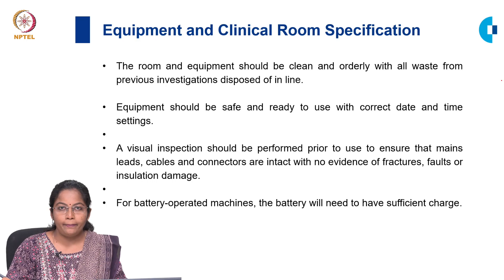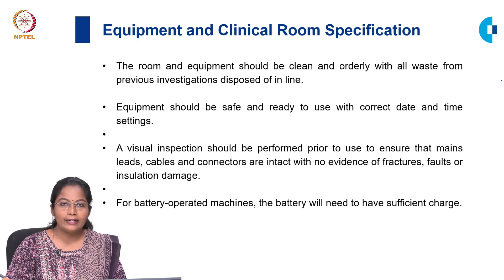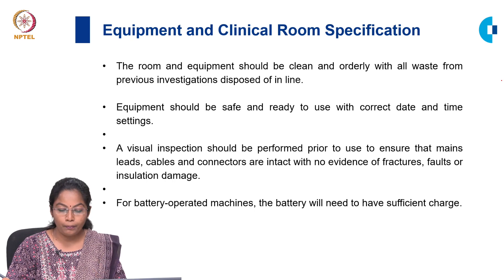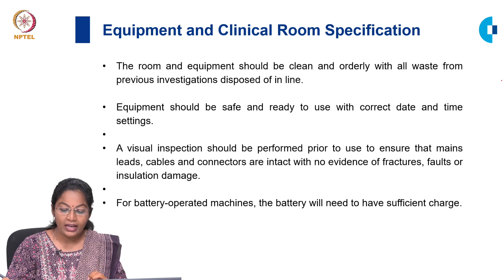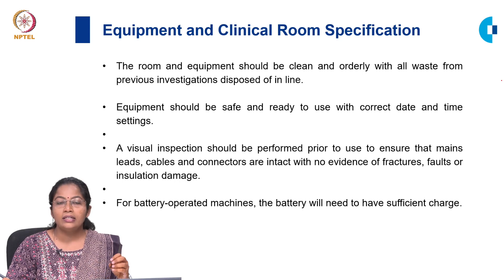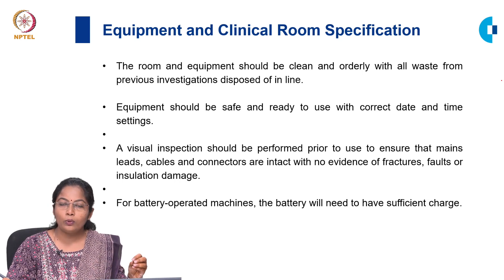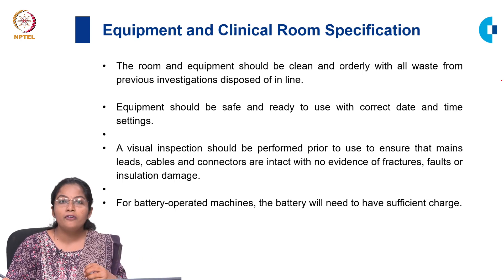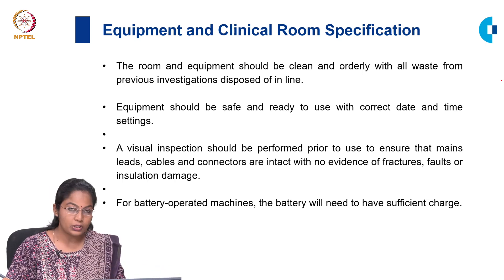Coming to the next step: equipment and clinical room specification. You should make sure that the room and the equipment are clean. The equipment should be safe and ready to use with the correct date and time entered. Also, you should make a visual inspection of the equipment such as the cables, wires and plugs, and rule out any faults in the machinery. For battery-operated machines, you should ensure that it is fully charged before the procedure.